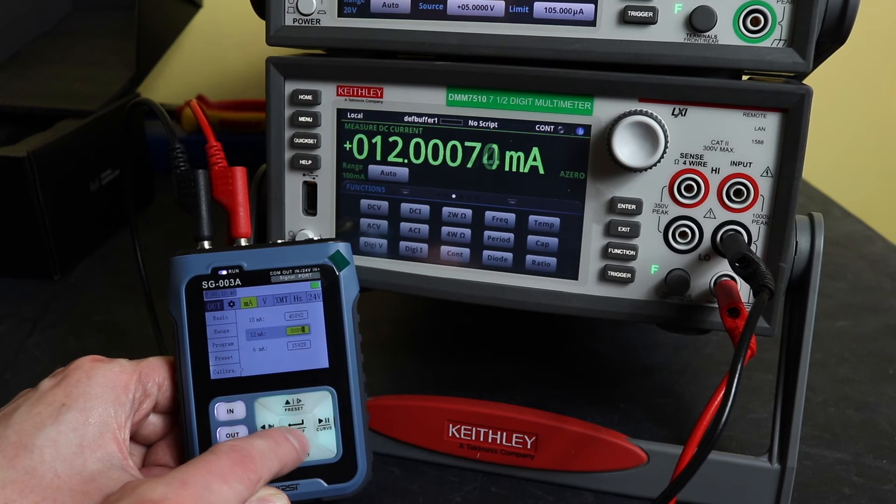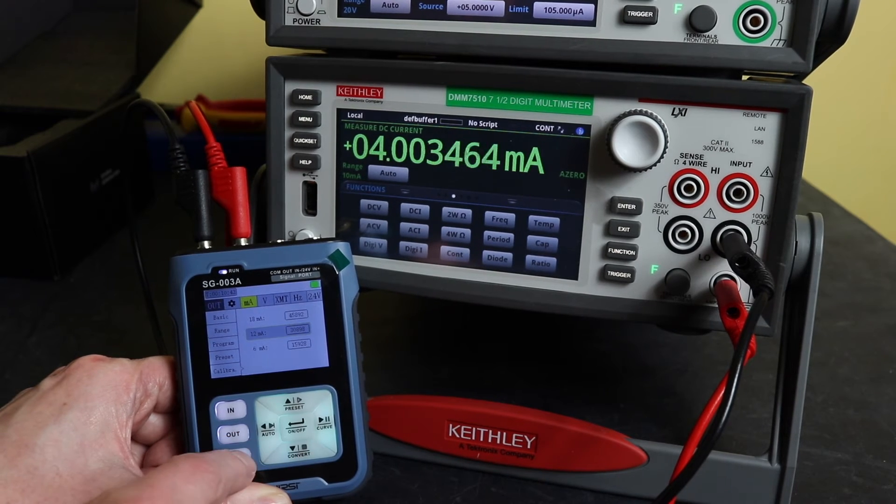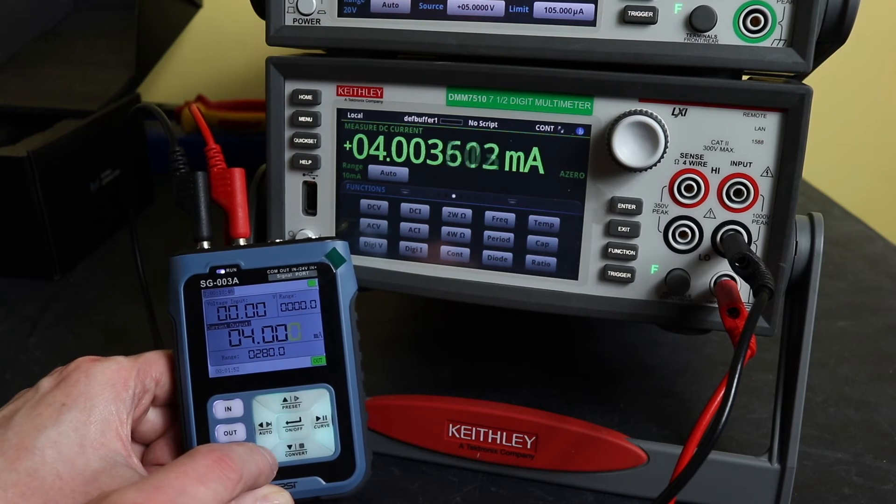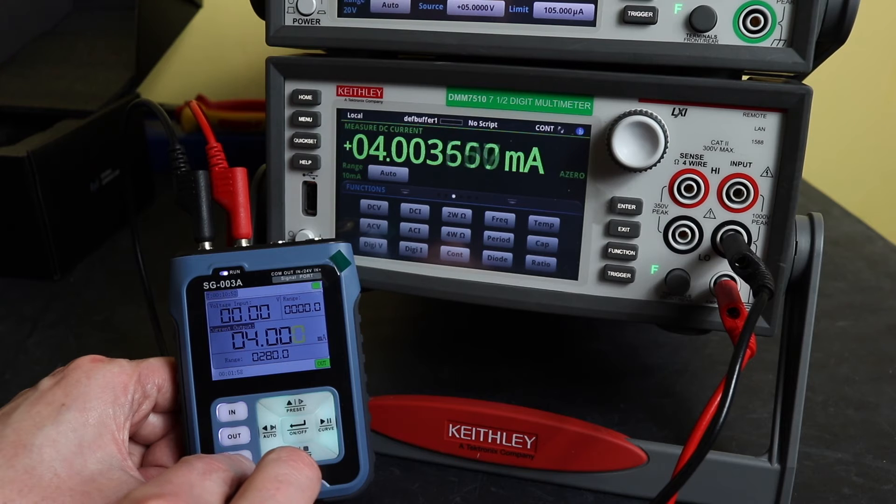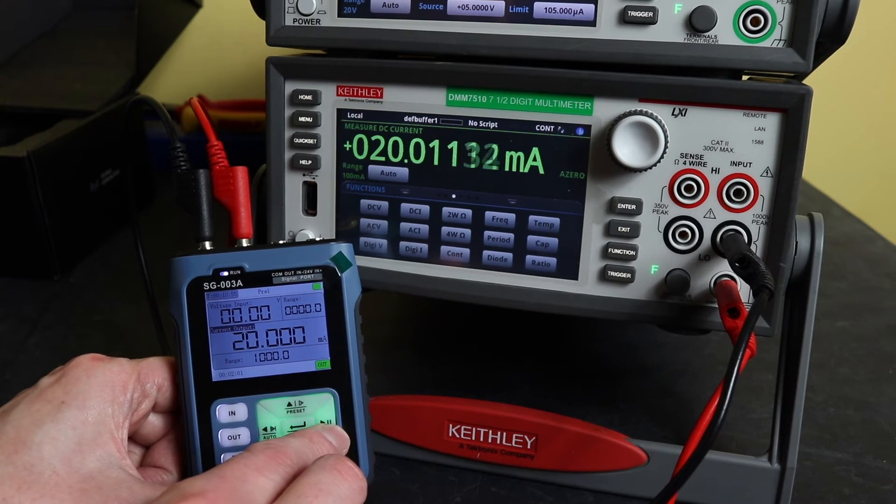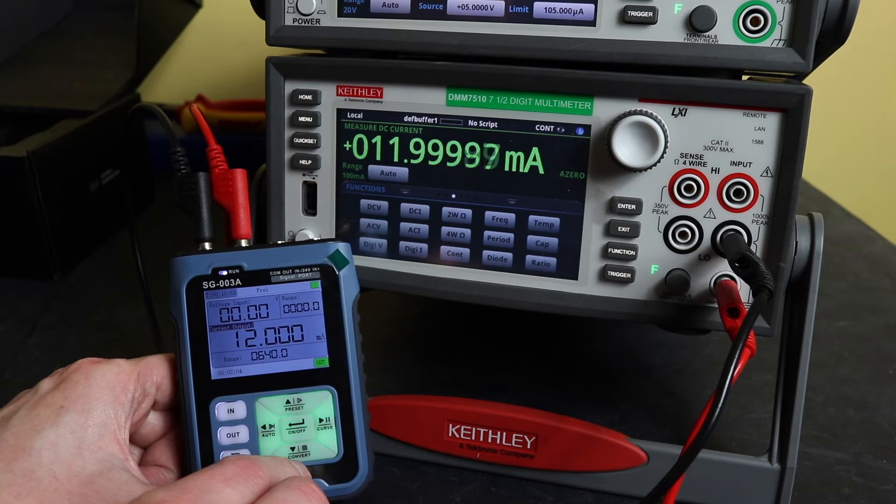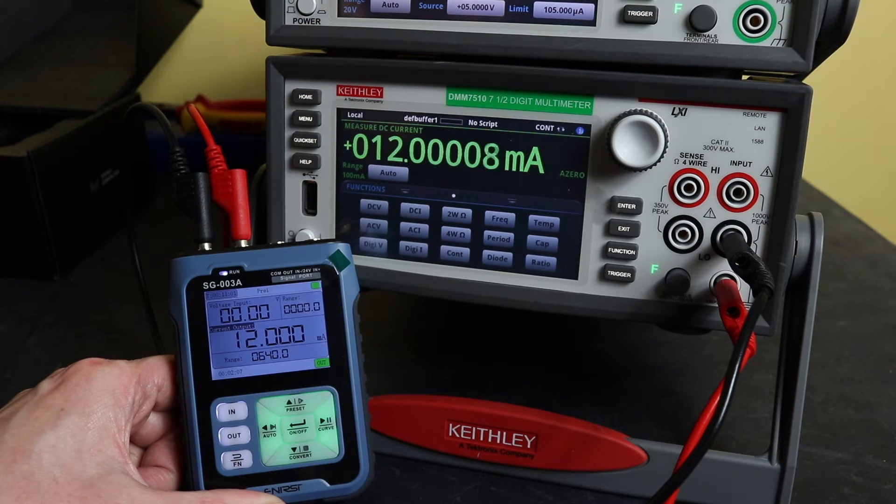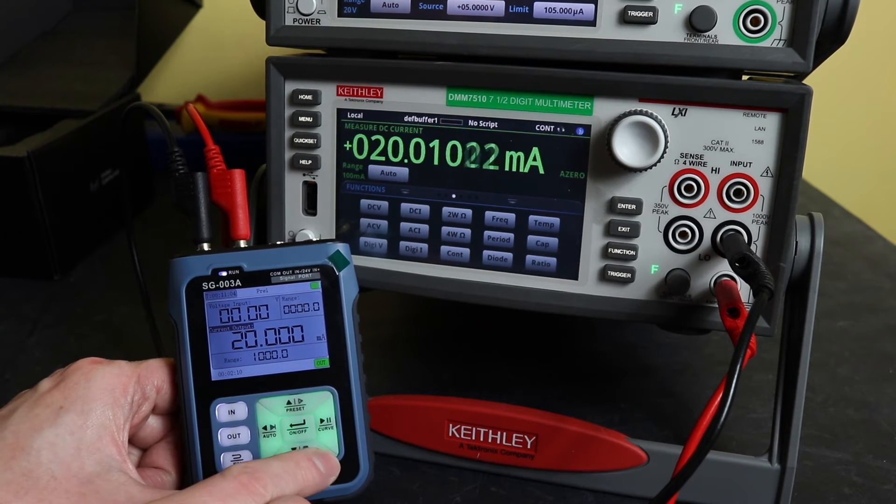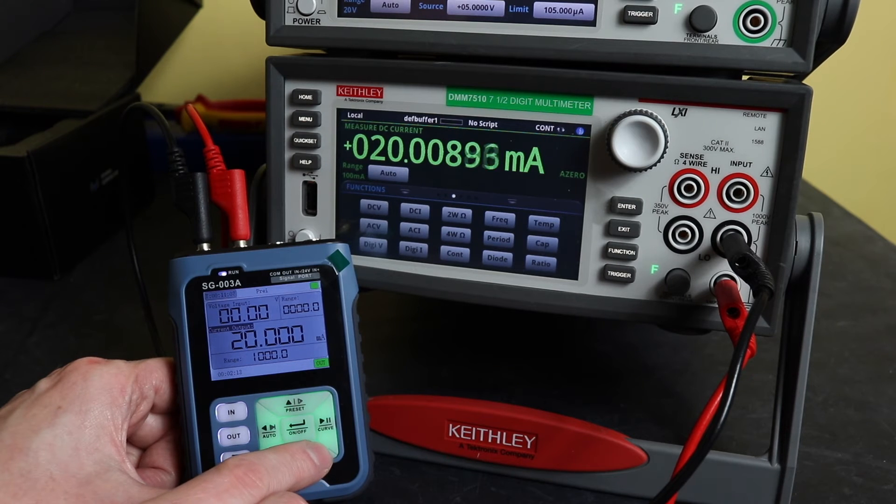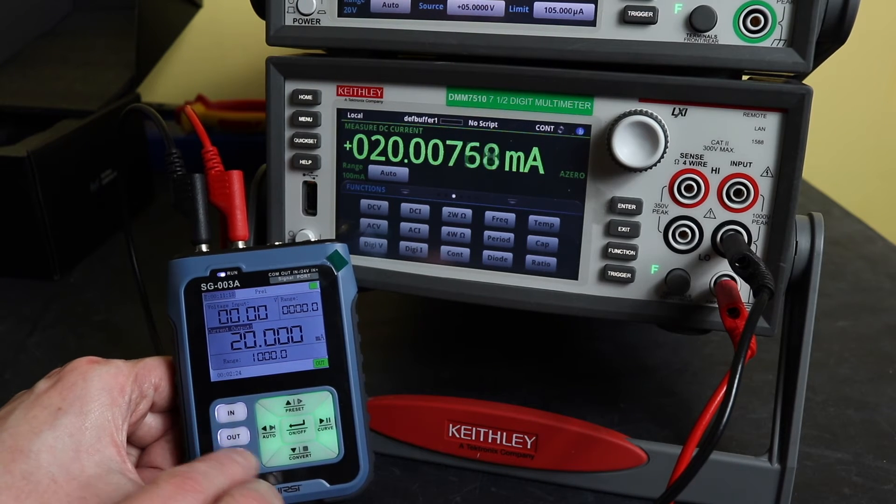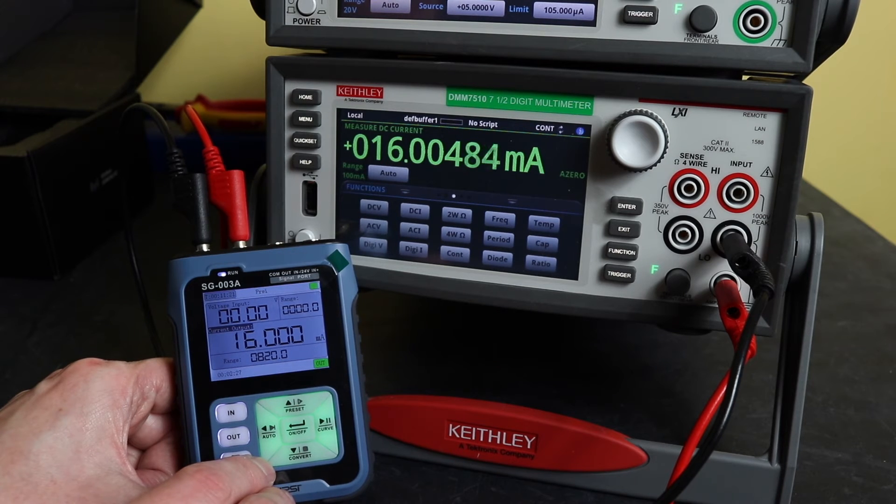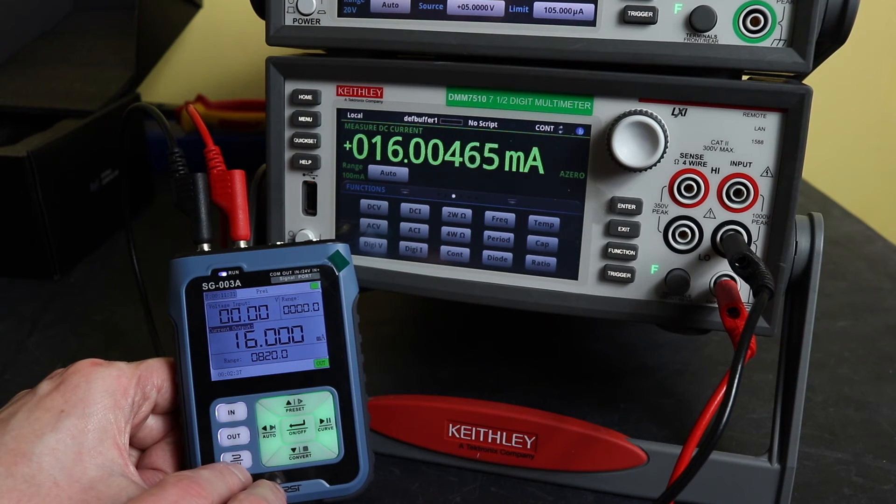And go back in there, and go back again. So 4 milliamps, let's go to what's my presets on this. 12 milliamps, so 12 milliamps, 11.99, 12-ish. 20 milliamps, 20.009. Yes, it's moved again from what I had in the past. That was, it's actually worse actually.